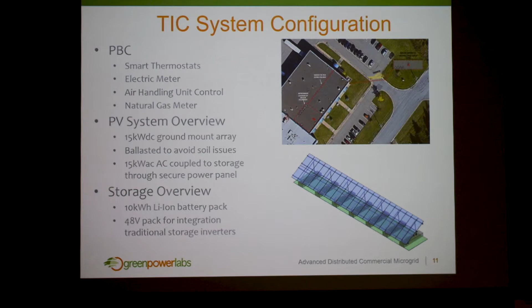We deployed a number of Nest thermostats throughout the building, and our PBC application is able to talk to those smart thermostats, so we can optimize heating and cooling. We also installed real-time electricity meters to feed that data into our algorithm. Since there's no BAS, the rooftop unit had no control device either, so we bought a small AHU control device, installed it, and we're able to control that separately through PBC as well. We're also in the process of sourcing a gas meter to deploy.